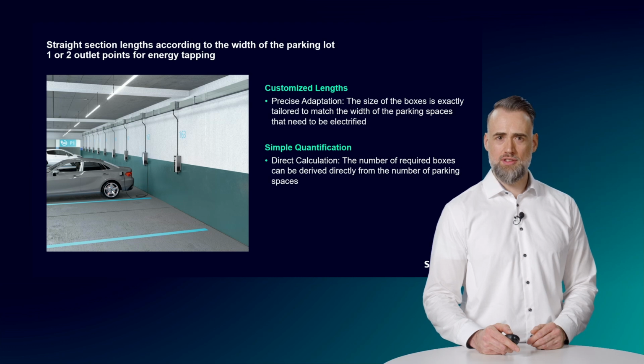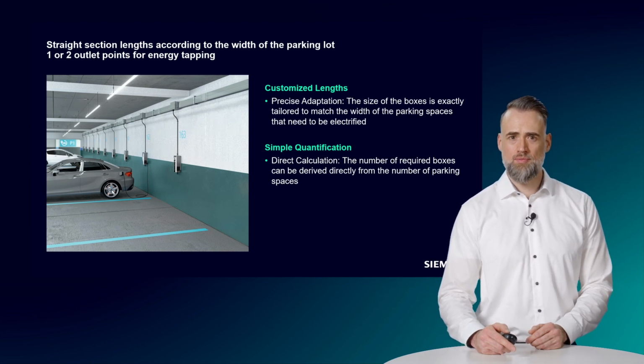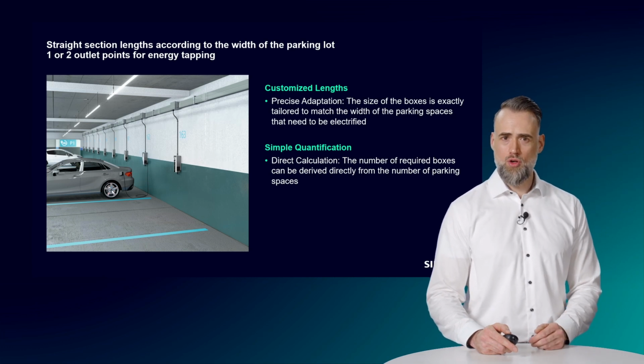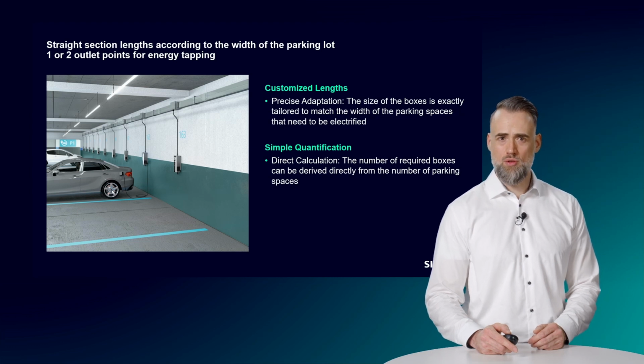The tap-off boxes are therefore always attached to the same position within the parking lot. You know the nominal power of the wall box and how it should be protected. With this information, you can simply select and order a tap-off box, optionally with fuseless or fuse-based technology, with or without residual current protection.